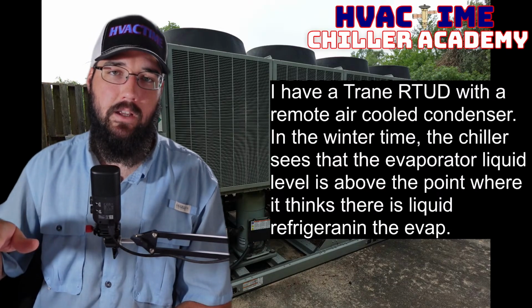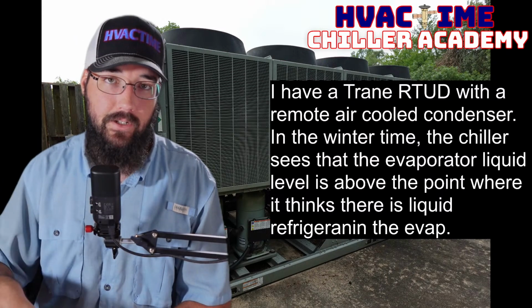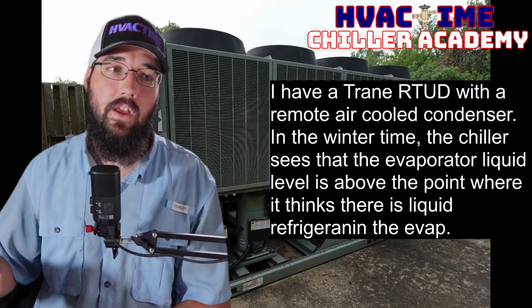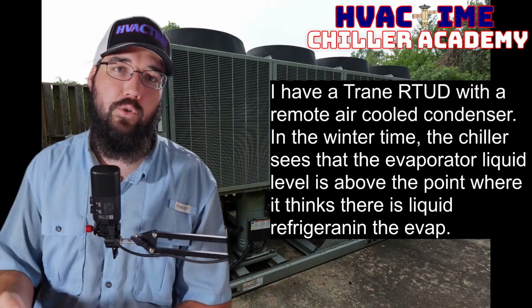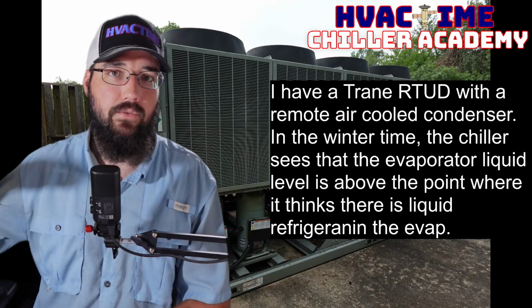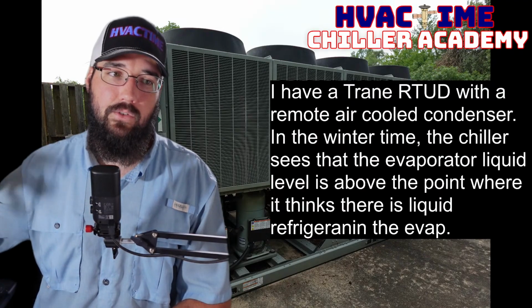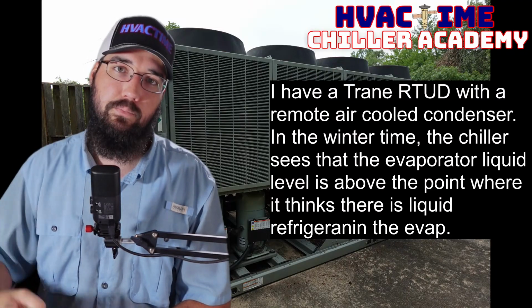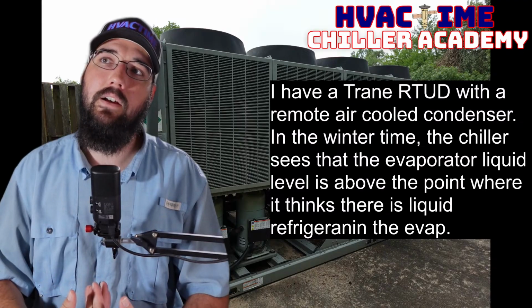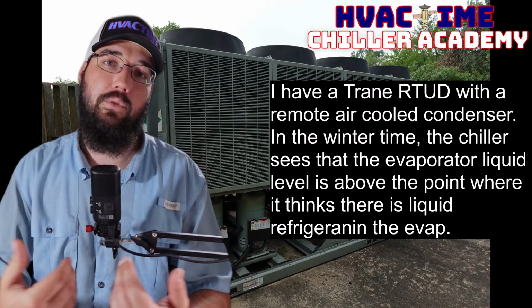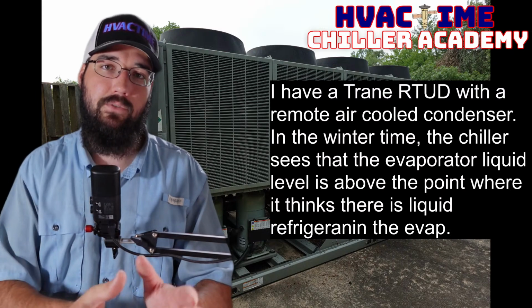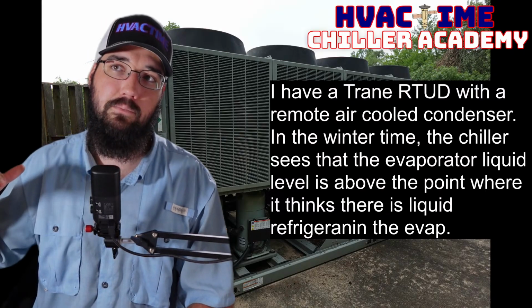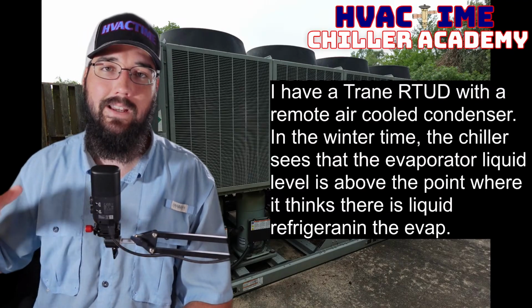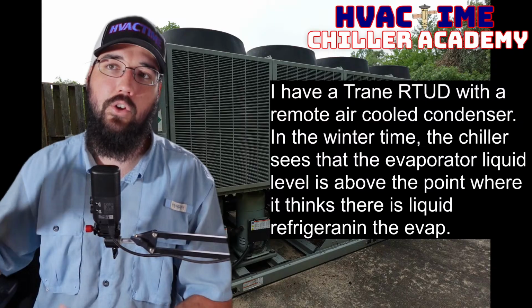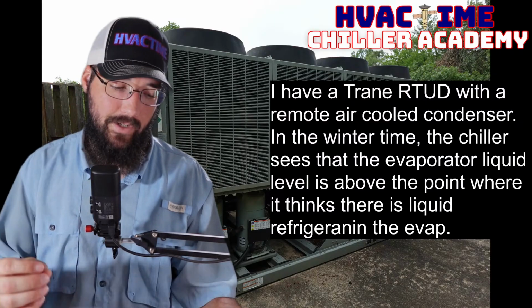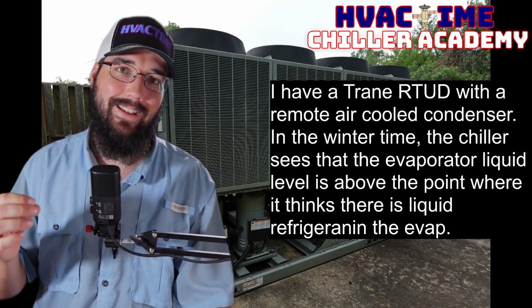So if you are not keeping that head pressure, if that PRV is not calibrated properly, and your condenser pressure is able to drop too much in low ambient conditions, you're not going to maintain good velocity through the system and a higher differential. Part of what that system needs to function really well is a little bit of a higher differential to push into that gas pump and force all of that oil-laden refrigerant back up to the compressor oil recovery line. So these things have to work in unison, which means we have to maintain enough pressure and velocity on the condenser side itself. If we do not do that, it could have issues doing the oil recovery process. So we need to make sure that you're maintaining condenser pressures.